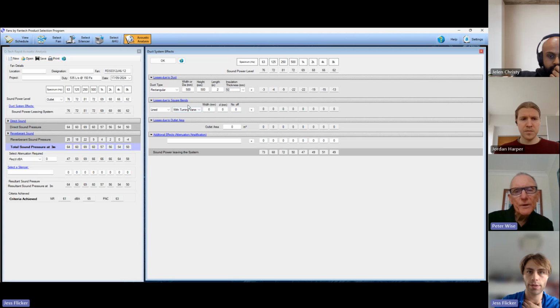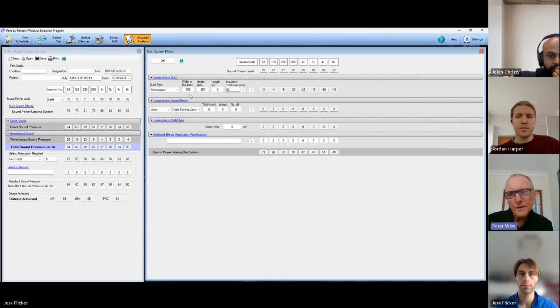So I'll just say what I was going to say before now. The ones that are the most nuisance in a building are the low frequencies, particularly 125 and 250. You're getting the lowest attenuation there because they're low frequencies. The sound has a high wavelength at the lower frequencies - you understand the relationship between wavelength and frequency. So it's always the most difficult to attenuate low frequency sound, and the low frequency sound is like a drumming sound, which you'll get from a fan. Just be aware of that as well, and I do mention that in the notes I sent you. We'll talk about that some more later.